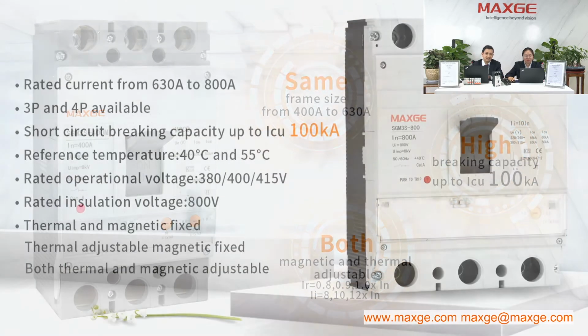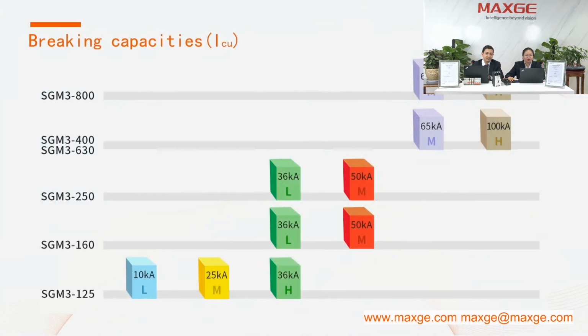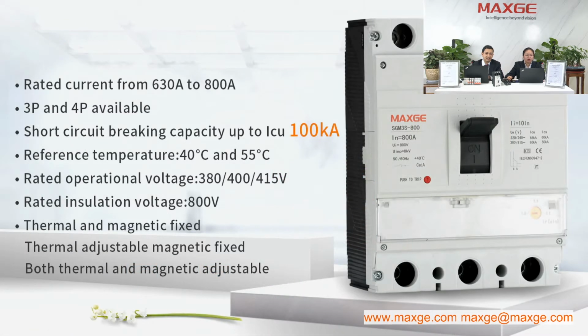The next one is for the SGM3 800 frame size. We have the rated current from 630 to 800 ampere, and also we have 3-pole and 4-pole, and we have the choice of fixed type and adjustable type.